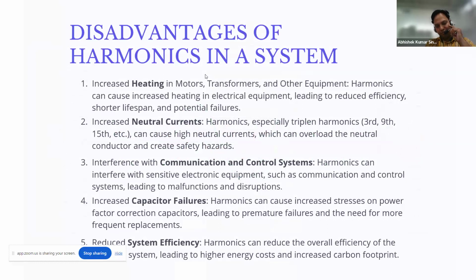Now, disadvantages of harmonics in a system. There is one more thing I would like to tell: always try to place the drives or non-linear loads near the source. If you place the non-linear load at the end of the panel, the harmonics will travel up to the source, so they will travel in the entire system. If the load is closer to the source, it will not impact the system much. But if it is very far away from the source, it will definitely affect your system. As we discussed, there is increased heating in the motors, neutral current will increase, and communication and control systems will definitely be impacted. Then there is capacitor failure, which we will understand in further slides, why capacitors fail in the presence of harmonics. And there is reduced system efficiency. Yes, because there is a lot of resistance, there will be a lot of losses in the system, which will definitely reduce the system efficiency.